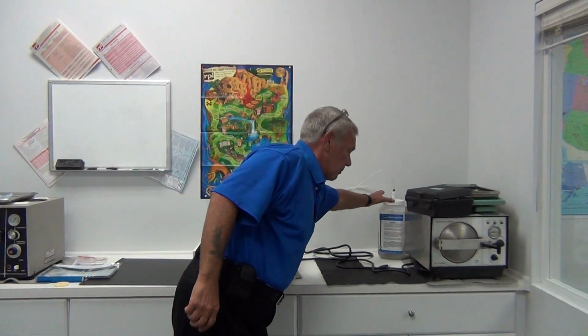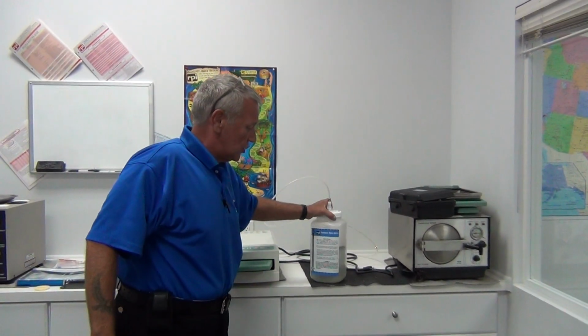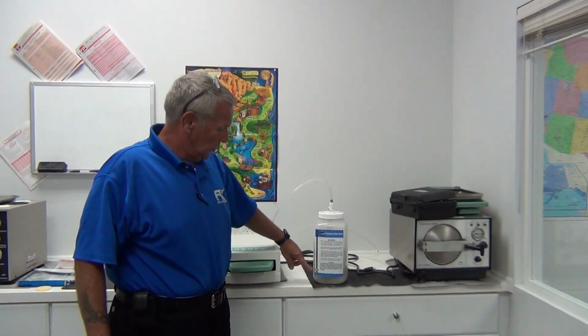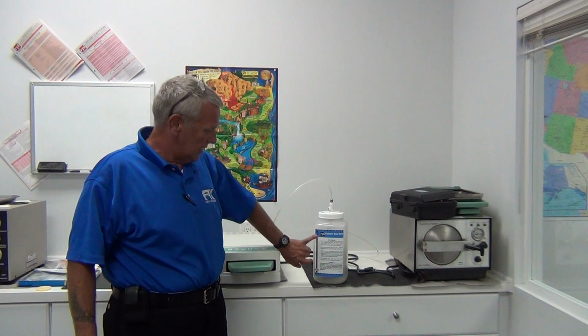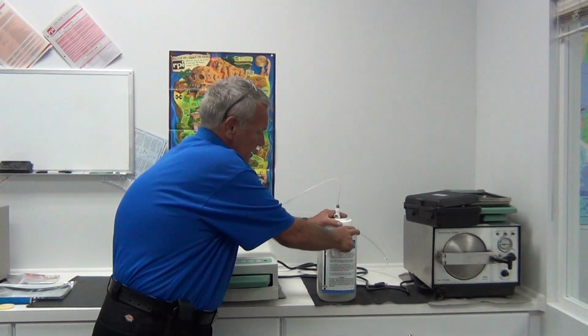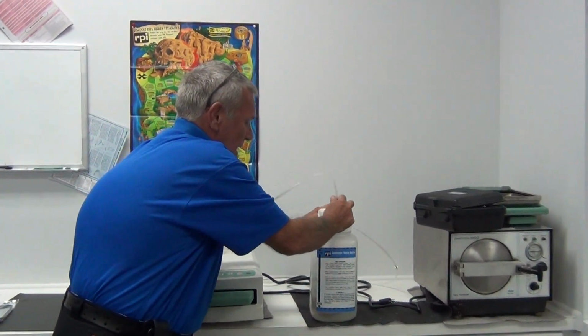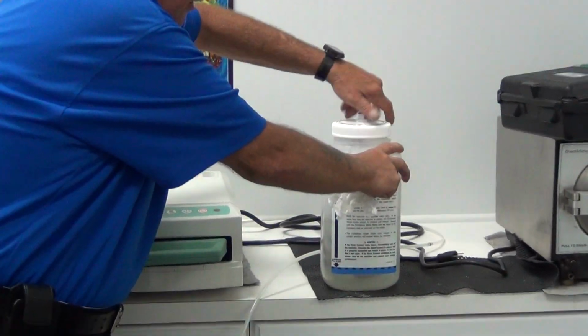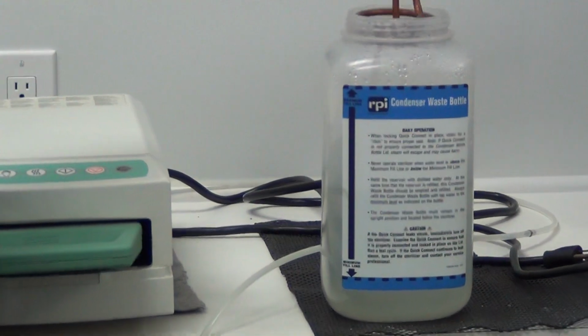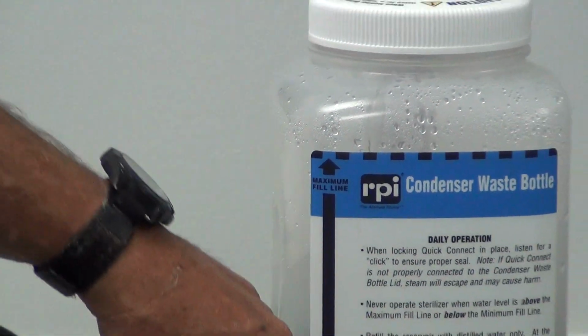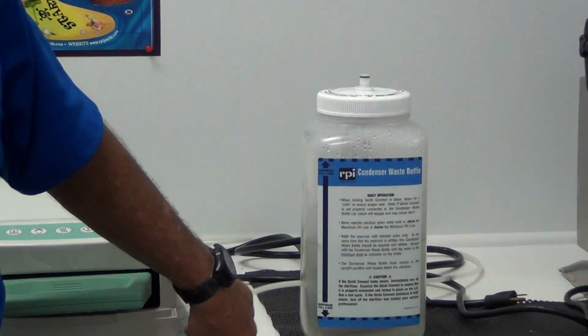First item of maintenance is your condenser bottle and your connections to the condenser bottle. If you'll notice on the condenser bottle, you have a maximum line on the top and a minimum line on the bottom. You must have a minimum amount of water in the collector bottle for the sterilizer to work. As you can see, there's a condenser tube attached to the inside of it. Without the condenser tube attached, the sterilizer will give you an error code every time. One of the items for maintenance you can do is simply empty the bottle into the sink and leave the water to the minimum fill line.